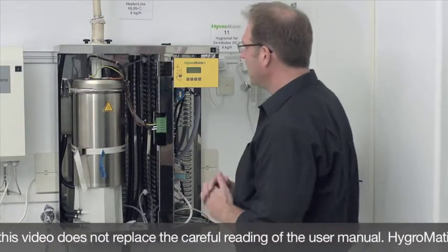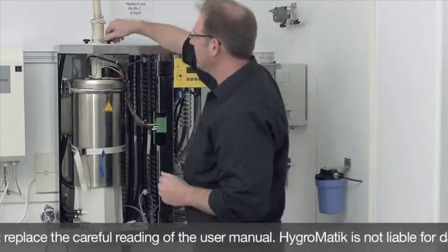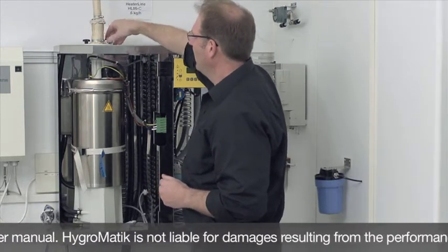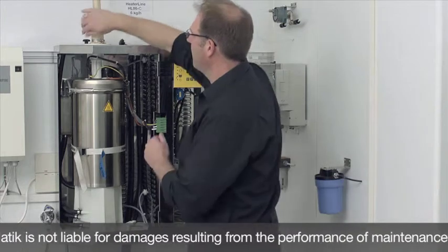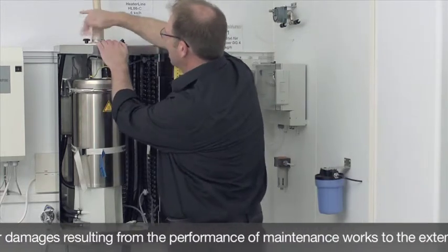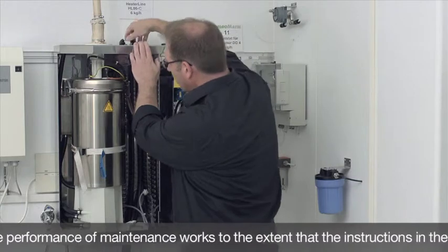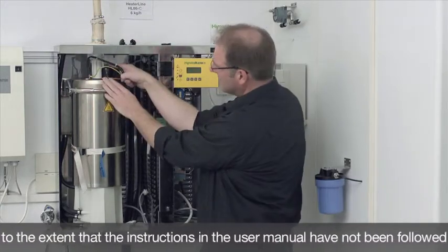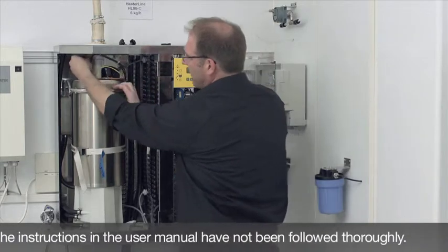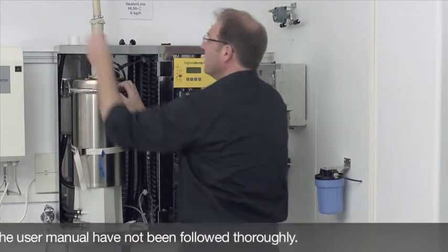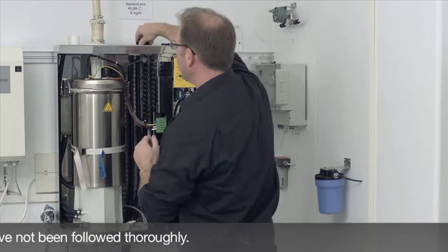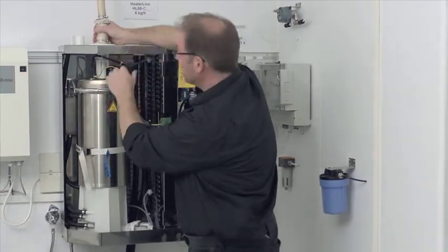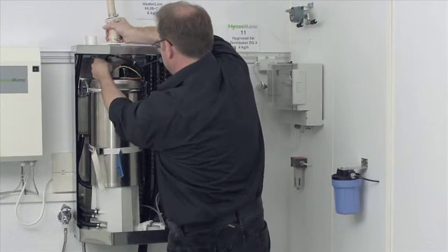I begin by disassembling the cylinder by first loosening the star screws on top here. And then here at the steam hose connector, that's the white plastic piece, I pull off the clip and place it up here at hand. I can reuse that shortly. And now I can already pull off the steam hose adapter together with the hose up at the top and out.